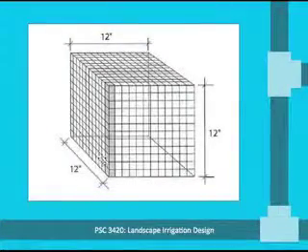So at the base of this particular column, this shaded column of square inches here, there are 0.433 pounds resting at the base. So that would also be equal to 0.433 pounds per square inch. And this is where we start getting into the terms relating to pressure, pounds per square inch. And 0.433 pounds per square inch is a constant that we'll be using a lot in the course. We'll go over it many, many times.